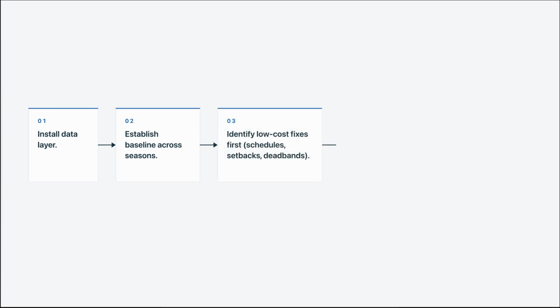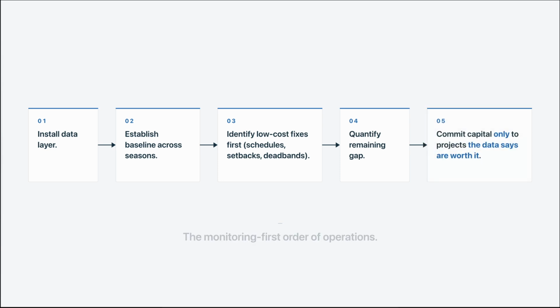The right order is actually simple. Install the data layer first. Second, get a good baseline across seasons, not weeks. And third, identify the low-cost fixes the data reveals. These could be schedule corrections, setback updates, and deadband adjustments. And then, fourth, quantify what gap remains between the corrected baseline and the performance the building should be capable of. And fifth, and only fifth after you've done the other 4 steps, commit capital to the specific projects the data says are worth committing to.